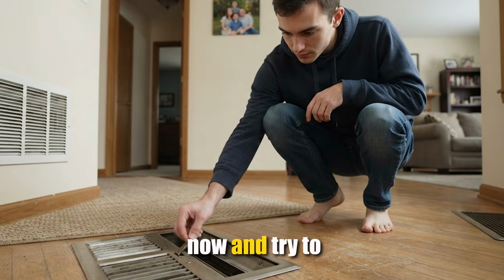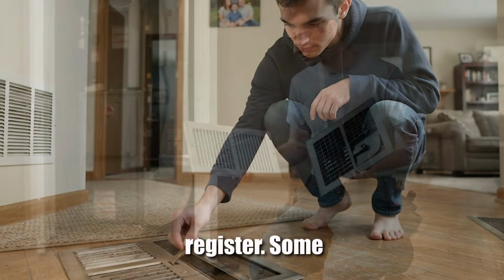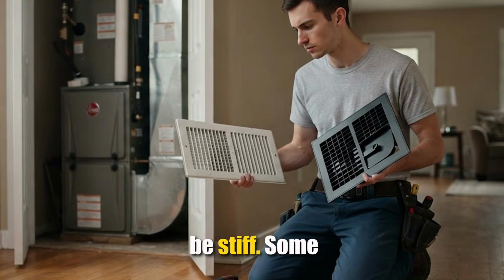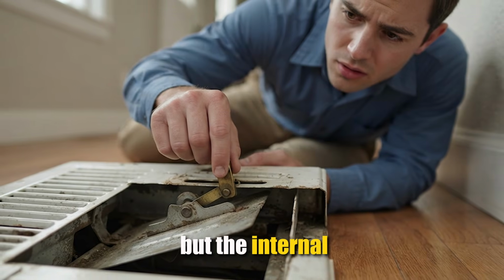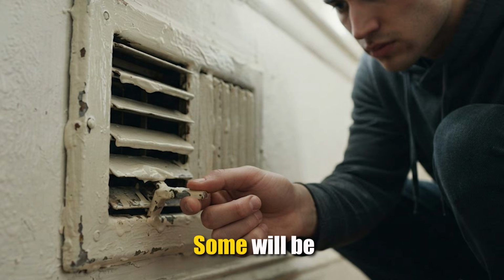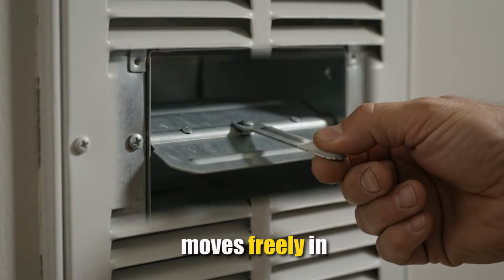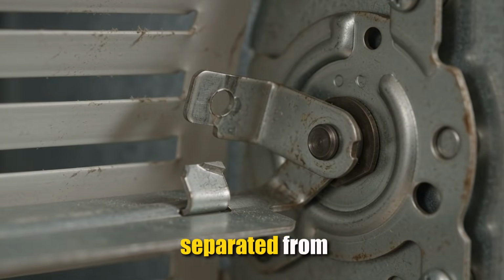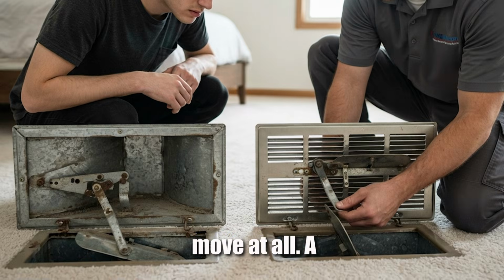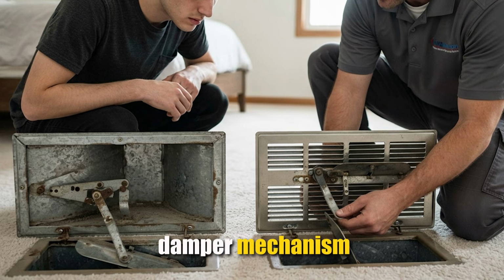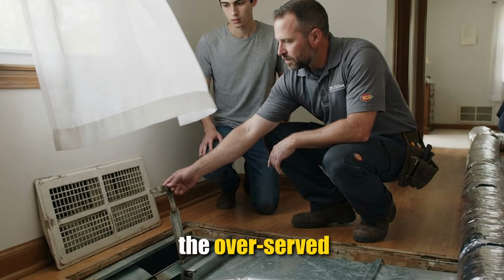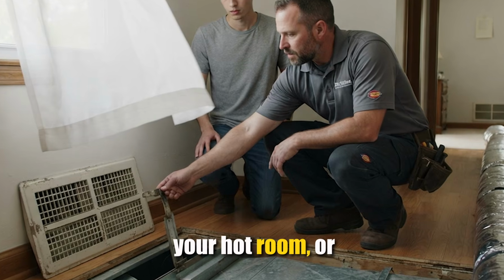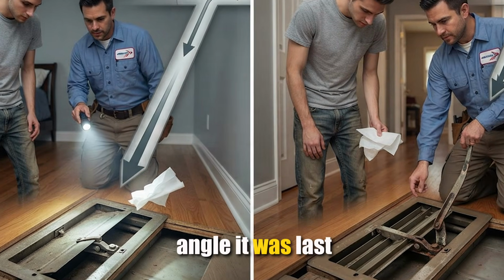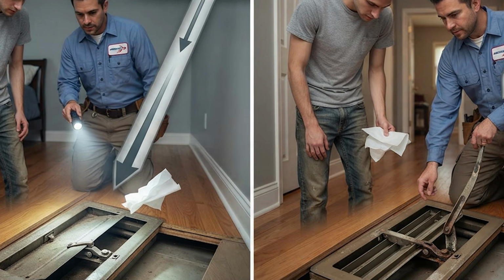Walk through your house right now and try to adjust the damper lever on every register. Some will slide smoothly, others will be stiff. Some will feel like they are moving, but the internal blade is not actually rotating. Some will be painted shut from every repaint the room has ever had. And some will have a lever that moves freely in both directions, but the blade inside has separated from the pivot and does not move at all. A register with a broken or seized damper mechanism is a register you cannot control. It sits either fully open, contributing to the overserved rooms that are stealing airflow from your hot room, or stuck at whatever angle it was last at, delivering the wrong amount of air indefinitely.